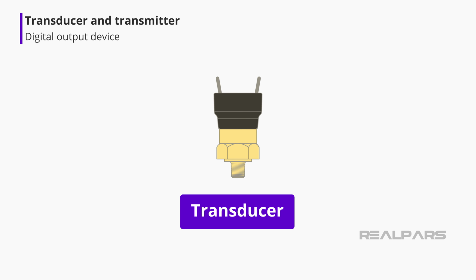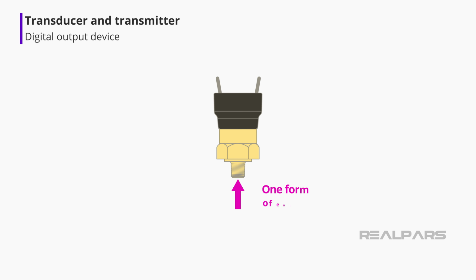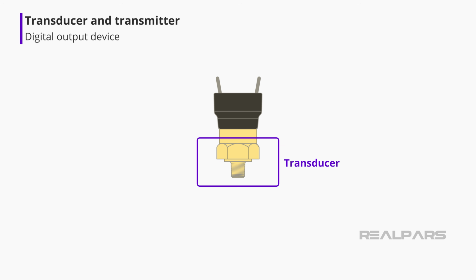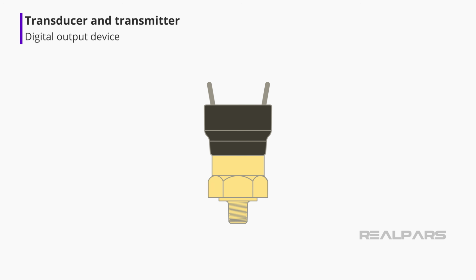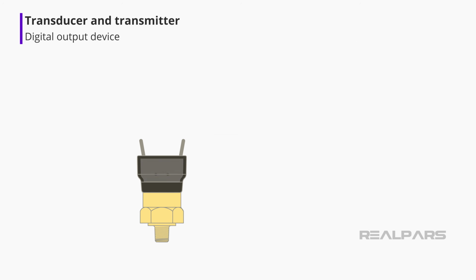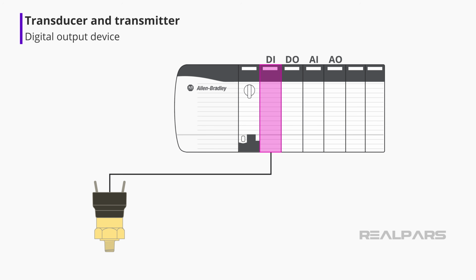A transducer is a device that converts one form of energy to an electrical or electronic signal. A pressure switch is a two-part device consisting of a sensing transducer and an electrical switch. A pressure switch is a digital device because it has only two possible conditions, open or closed. It is therefore connected to a PLC digital input module.